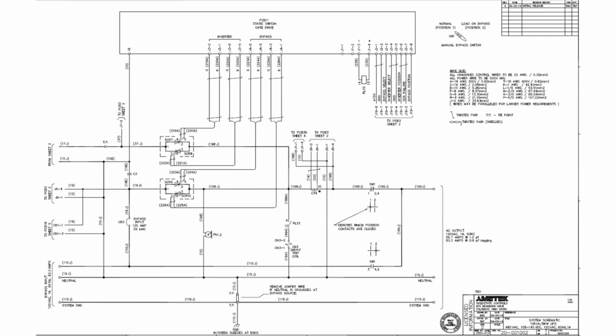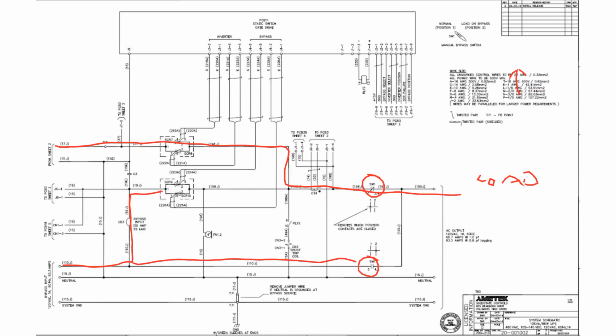You can see right at the top there, it just shows you what position the switch is in. So in normal position, it's saying that this switch here is in position 1, so it's closed, and this switch here is open. So that means in normal operation, power would be flowing through the inverter static switch down here and then out through this contact here to the loads. Our bypass supply is coming in here. It is ready to go at that static switch, but it's also coming along here and it goes to that side of the contact on the switch, but it can't go any further because that switch is open. So in normal operation, that is the arrangement of the manual bypass switch.